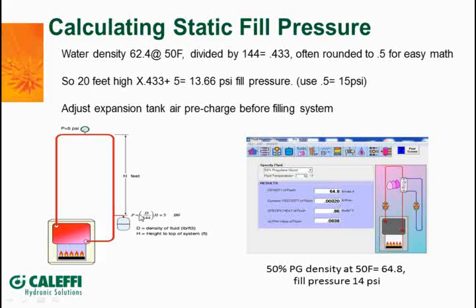So what we want to do is use this formula right here. P is the pressure that we need to fill it to. What we really need to know is the density of the fluid that we're going to put in there. If it's water, if it's glycol, it changes a little bit. I'll show you that here in a minute. So density divided by 144 times the height of the building. H is the height, and there's that 5 pounds that we want at the top of it, plus 5 pounds.